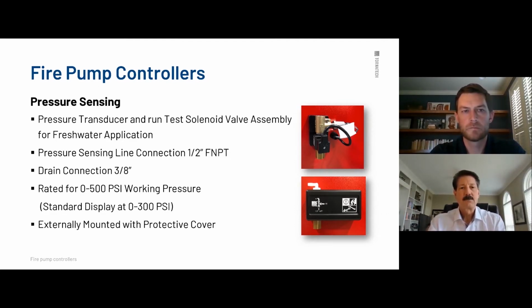As far as the run test solenoid, that is something that is used quite often. As we'll point out down the road here, there is a manual run test, and that would be actuating that test solenoid to drain a little bit of water, activate the system, drop the pressure, and do a test as required by NFPA 25, whether it's 10 minutes for electric or 30 minutes for a diesel. What it actually does is save a lot of water, because you don't have to sit there and open a valve and drain a substantial amount of water for that pressure to drop down to exercise the controller. And that's primarily the reason why that test solenoid is there, attaching to the manual run test button, is to meet your NFPA 25 requirements.